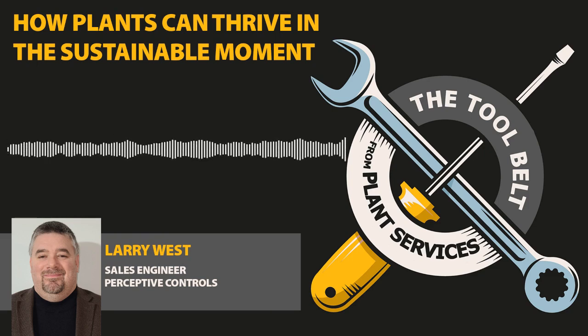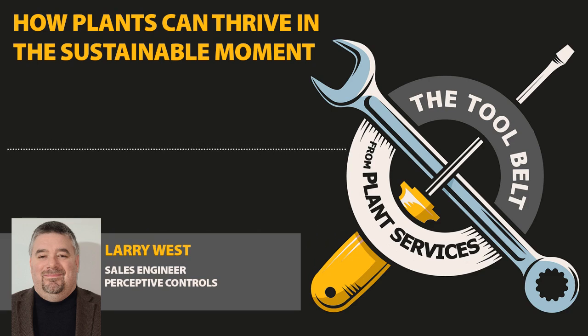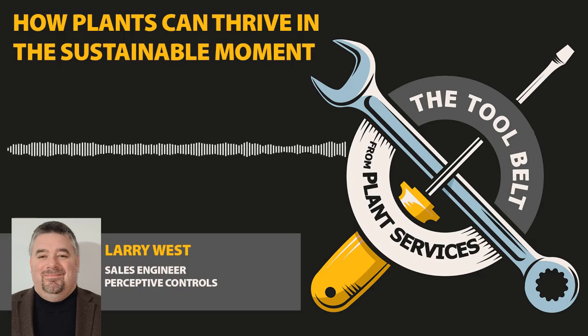For instance, if I'm a sugar producer, it is very likely, if I'm not in a climate controlled building, that in the summertime, if I'm in a high humidity area, I'm going to have more conveyor issues. I'm going to have more operational issues because that humidity is having an adverse effect on my sugar and how it's being able to move through the system. SCADA is one of those things that can measure those things for you and tell you what's going on. So if I know the humidity is getting high, I know I better change my process or turn the air conditioners on to make sure I get that humidity out of the room. So that way my sugar will flow. Many products, many powders, many granulates have the same effect with humidity. And that's where SCADA can come in and give you those useful tools to tell you how operation is.